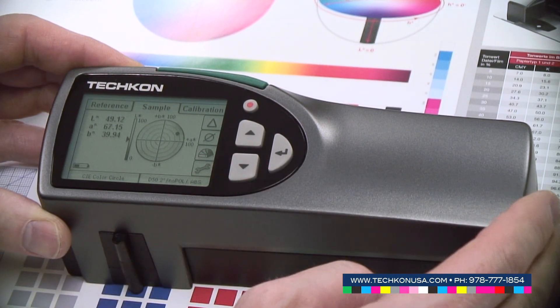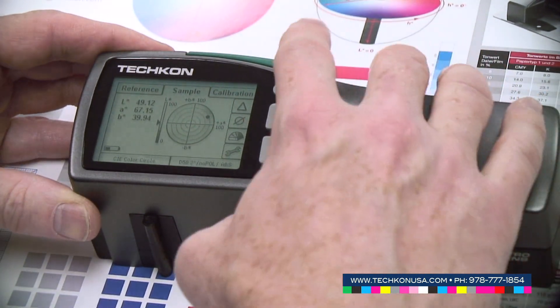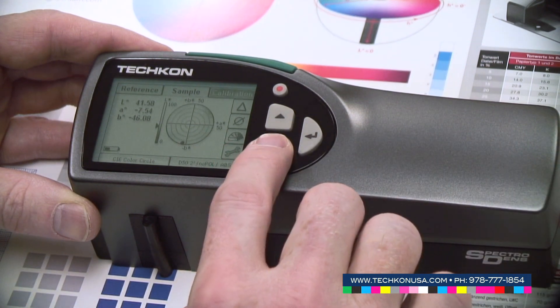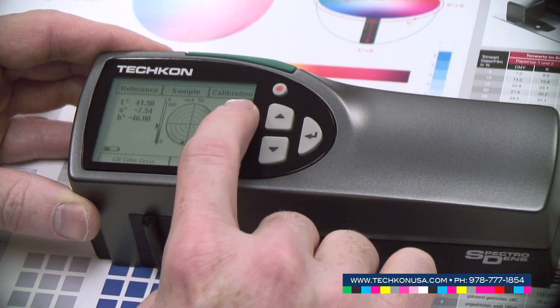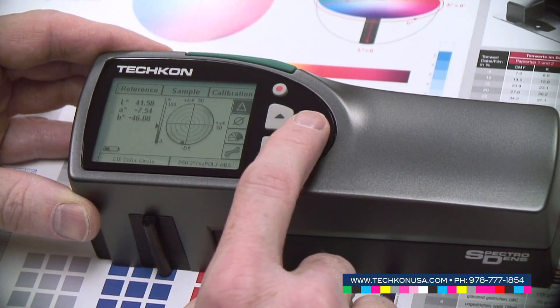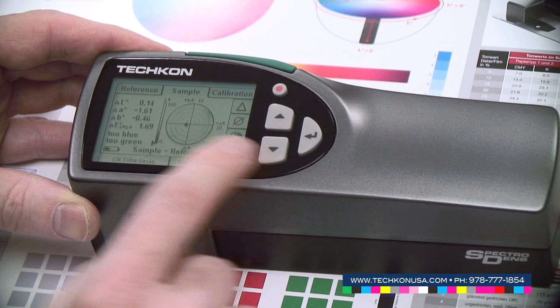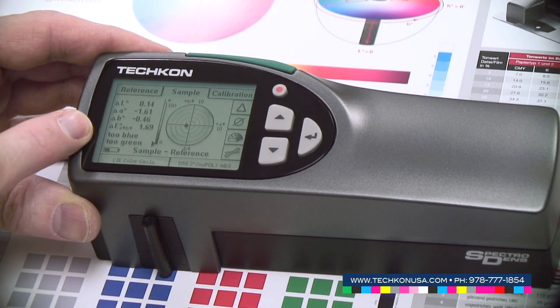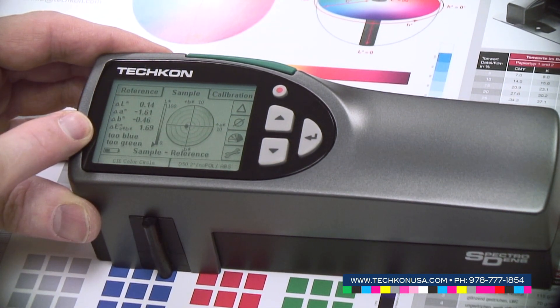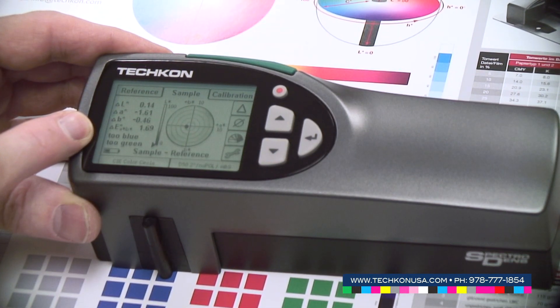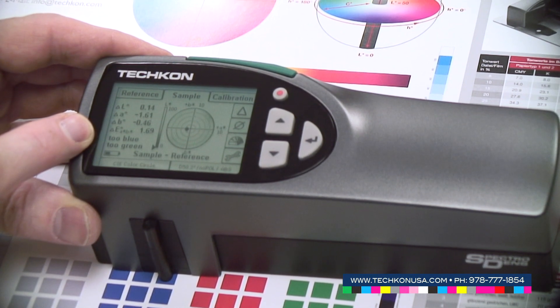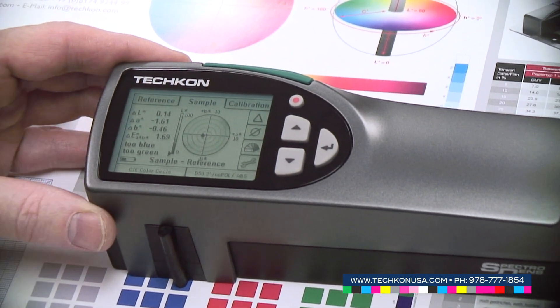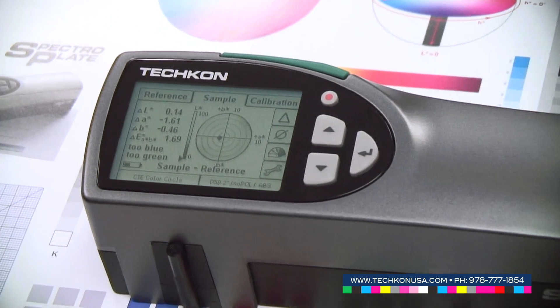We are changing to sample and we take another reading. Now we turn on the delta mode again with this triangle symbol. And now we get the deltas but also the information in which direction the colors are moving. So this blue is too bluish and a little bit too greenish — we can see this in the color circle.